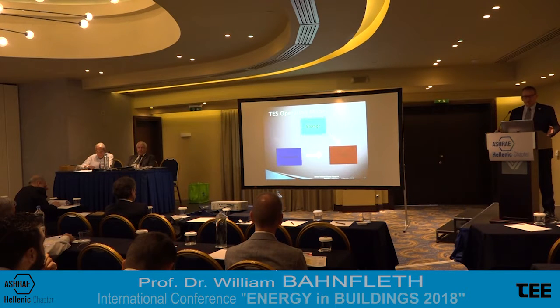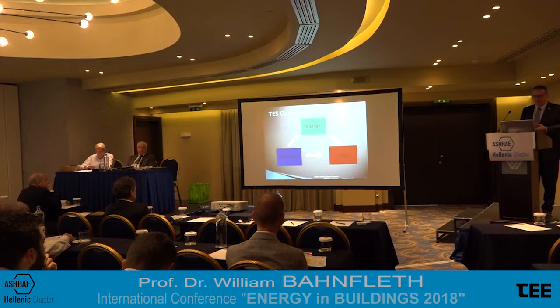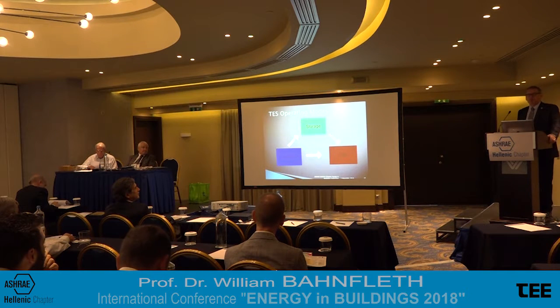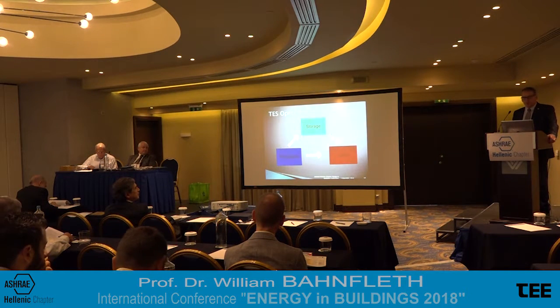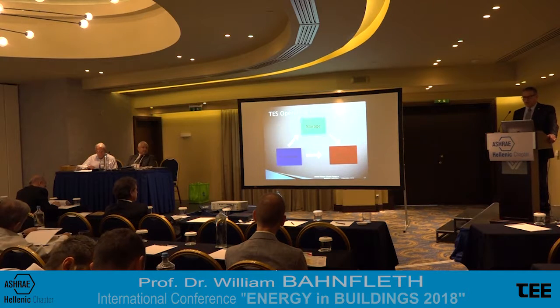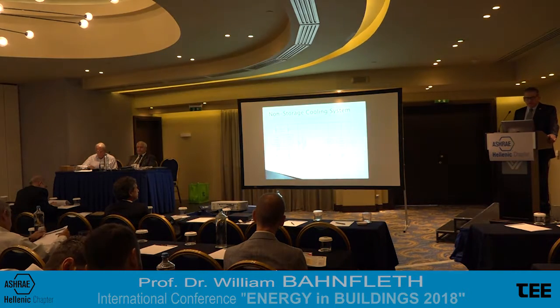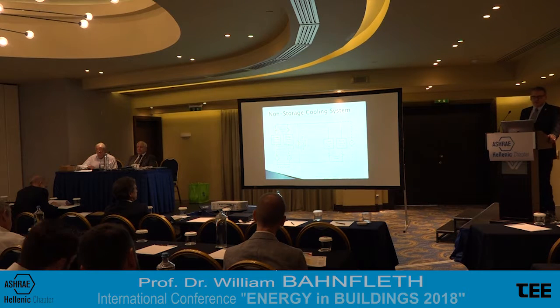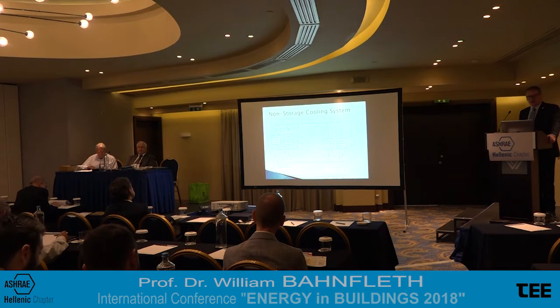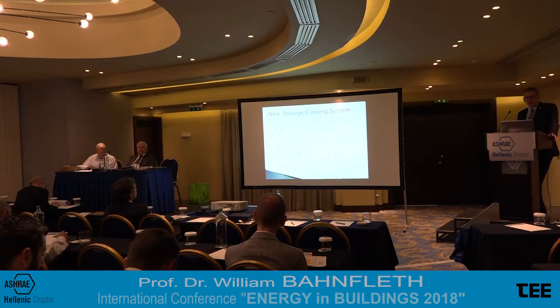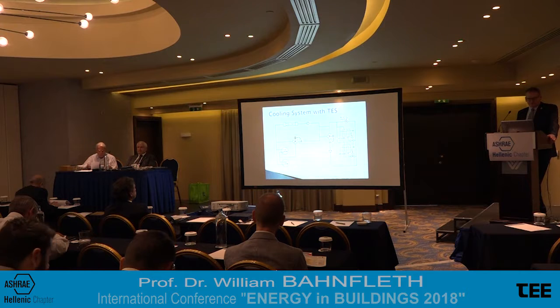But of course, to be able to do that, we have to have a point in our cycle where we put cooling into the bank, if you will, which complicates the system's design and operation a little bit, but actually not terribly much. Again, we see that just in the structure of the system. Here's a non-storage cooling system, and we can see the direct connection between the plant on the left and the loads on the right.